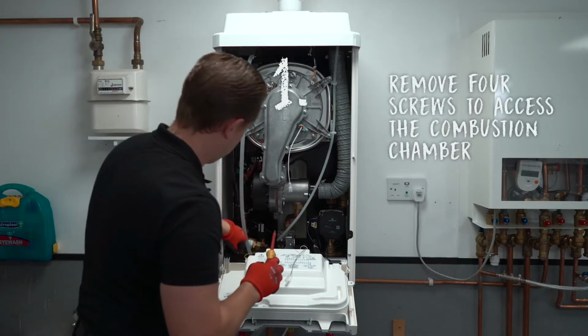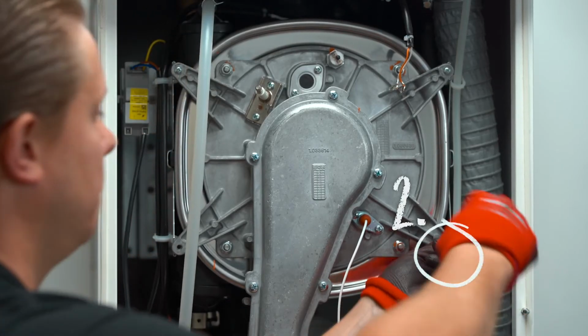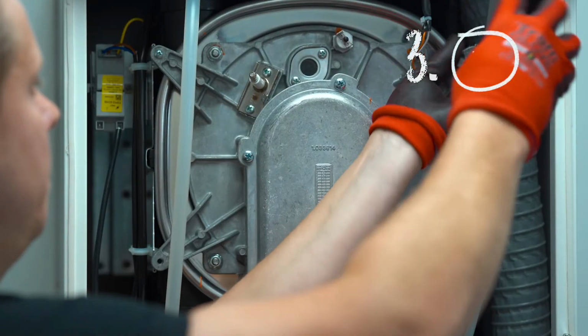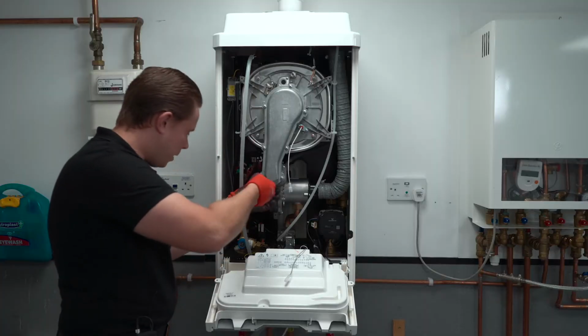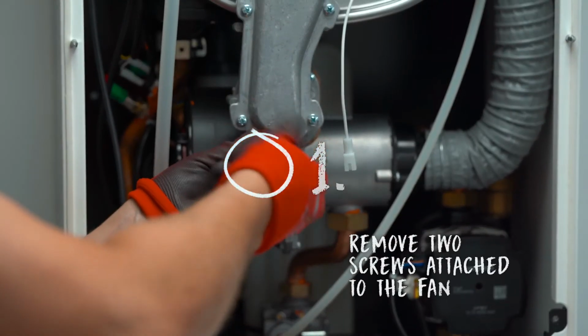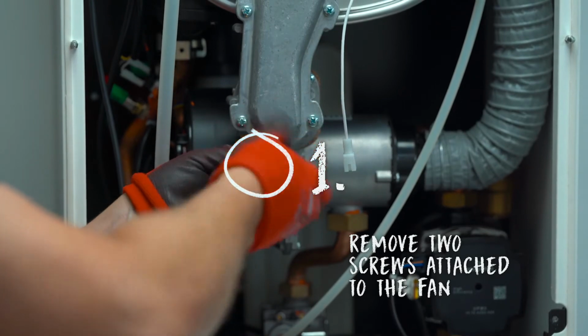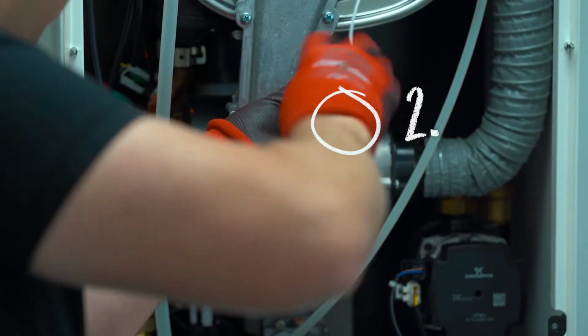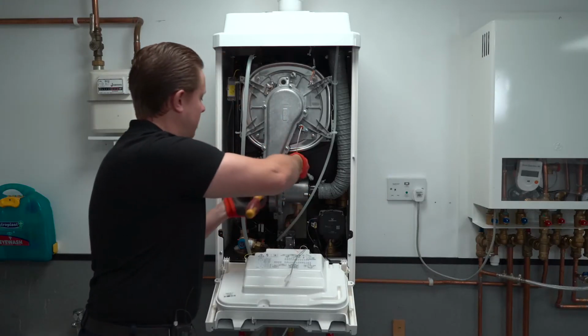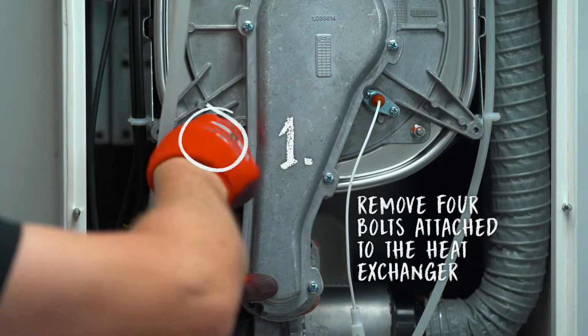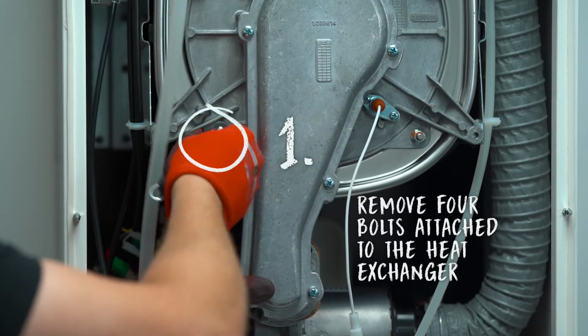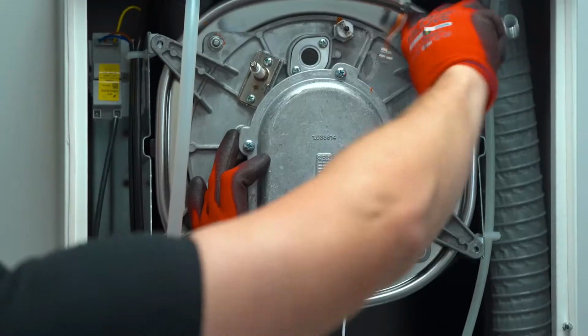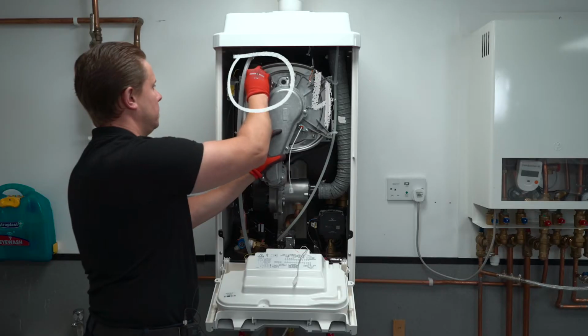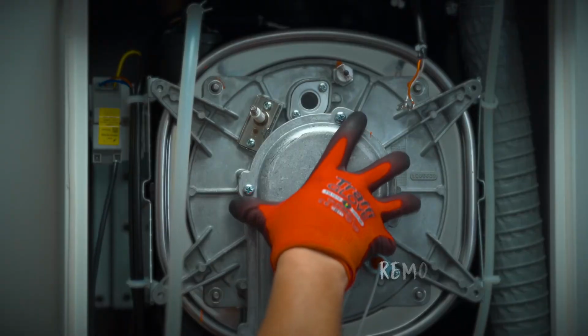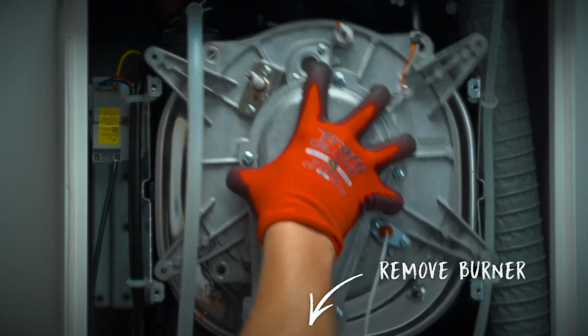Remove the four screws on the outer case of the combustion chamber door. Then remove the two screws which attach the burner to the fan housing. Using a 10mm ring spanner, take off the four nuts securing the burner to the heat exchanger. And then remove the burner from the boiler.